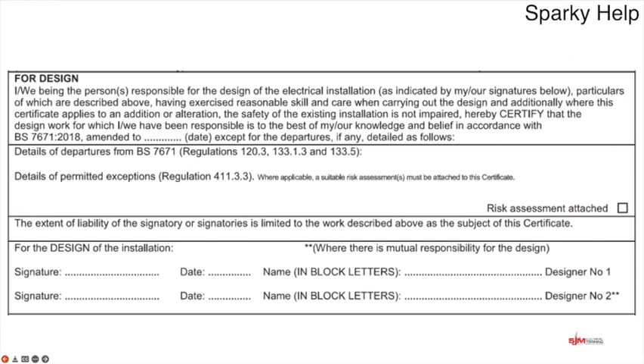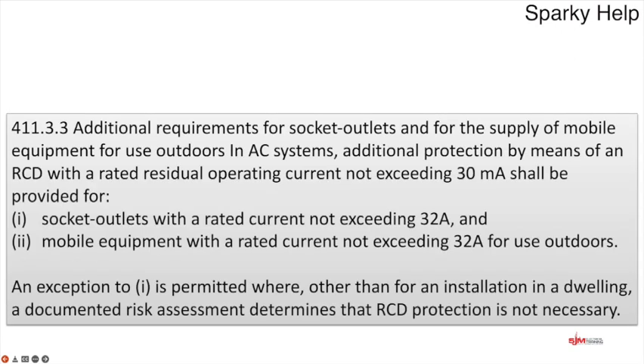It says details of permitted exemptions, and it takes us to chapter 41 of the regulations, 411.3.3. Where applicable, a suitable risk assessment must be attached. This bit, I believe, is going to go in the next regulations, but this particular one says additional requirements for socket outlets for the supply of mobile equipment for use outdoors in AC systems. Basically, you've got to put an RCD on it, a 30 milliamp. And the top one there, number 1, it says socket outlets with a rated current not exceeding 32 amp. And it says under the very bottom, it says an exception to number 1, i.e. the 32 amp one, is permitted where, other than for an installation in a dwelling, so that's a domestic installation, a documented risk assessment determines that the RCD protection is not necessary.